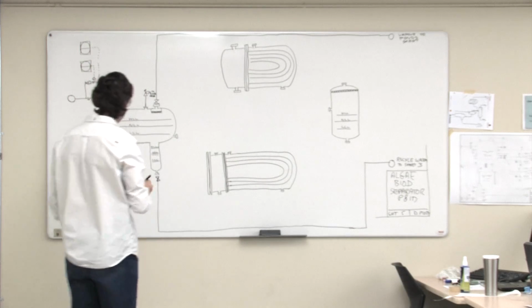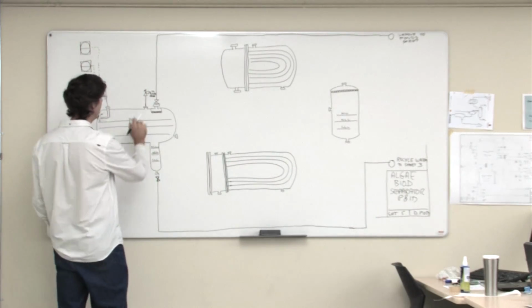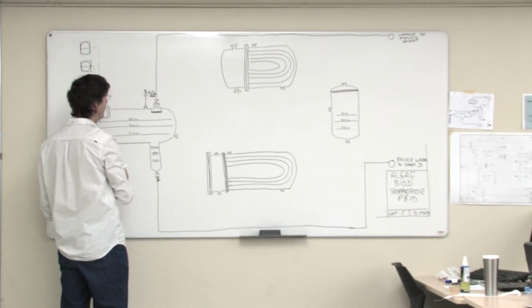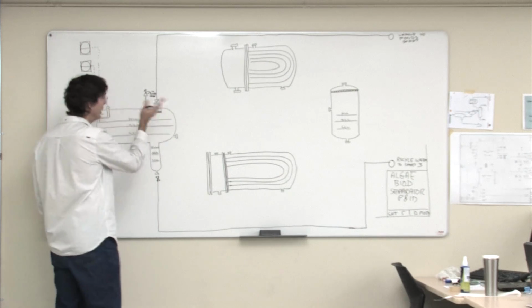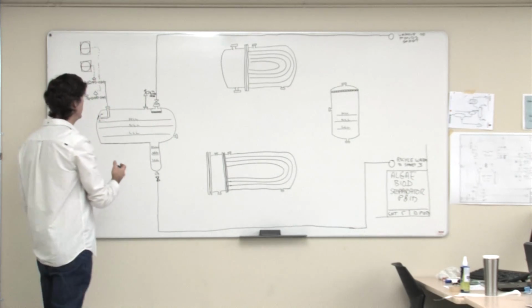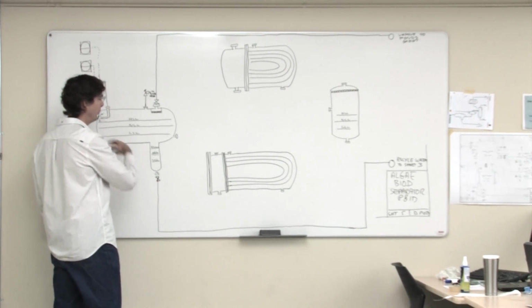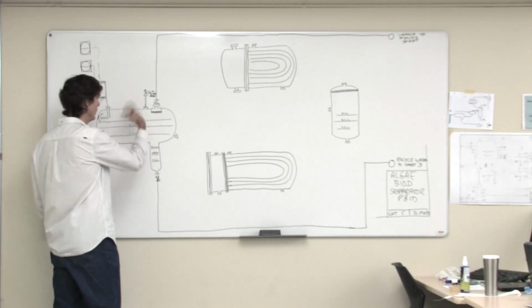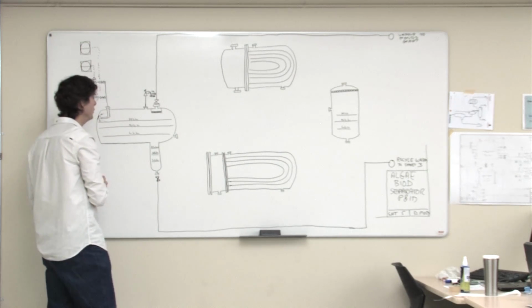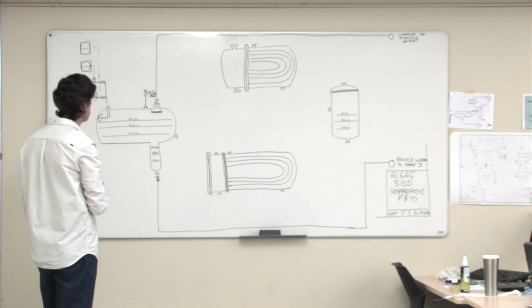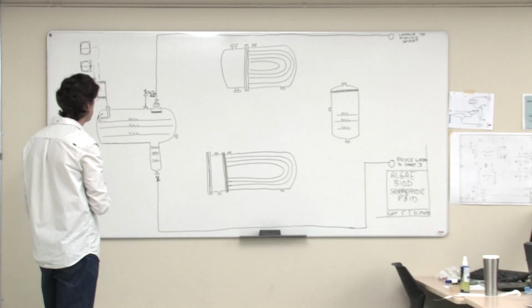I'm not going to put an isolation valve on that relief valve. We need to do maintenance on it about once a year, so I'll just shut the process down. We're going to shut the process down in the wintertime anyway, so I don't need an isolation valve there; we'll just do maintenance then. That makes it a little bit safer.